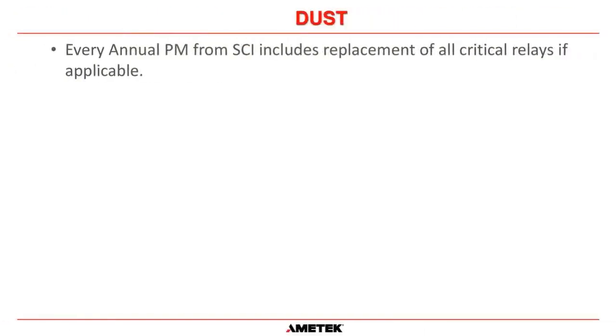And what we recommend is that every year, if you're going to get a PM done by one of our field service guys, all the critical relays inside that UPS will be replaced. Okay, it has to be critical to the normal operation of the system. I'm not talking about alarm relays or something like that that just gives you an alarm. All the critical relays to keep the inverter on load circuits with the battery backup, all of those should be replaced on an annual basis. Once again, there's always a good reason for why we recommend what we recommend.